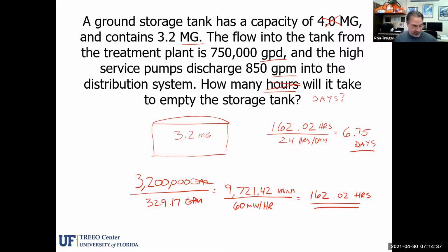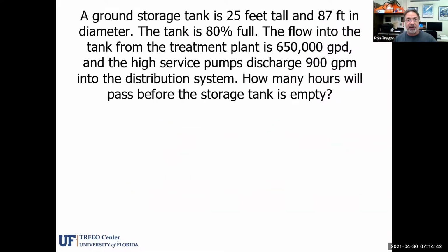All right, so here we go. We've got one more to do. Let's work out something that's probably the more complicated part of this, and this will take us a few seconds more. So we've got a ground storage tank. It's 25 feet tall, 87 foot in diameter. The tank is 80% full. The flow into the tank from the treatment plant is 650,000 gallons per day. And the high service pumps discharge 900 gallons per minute into the distribution system. How many hours will pass before the storage tank is empty?